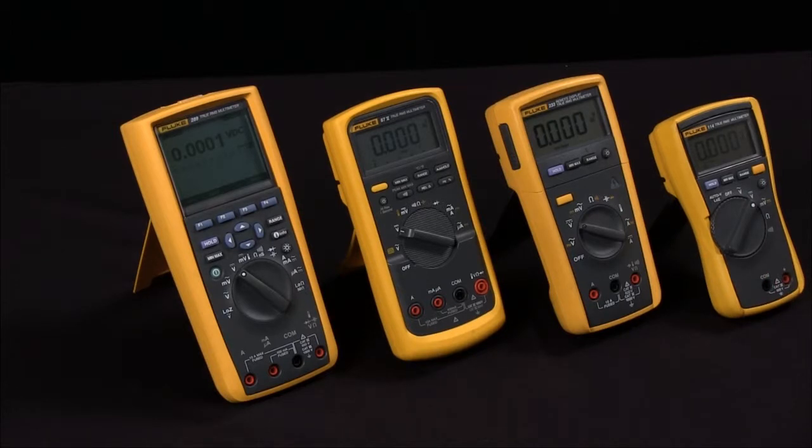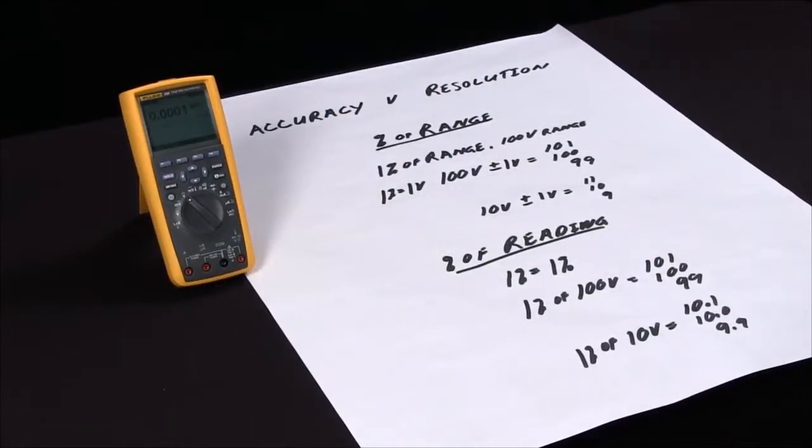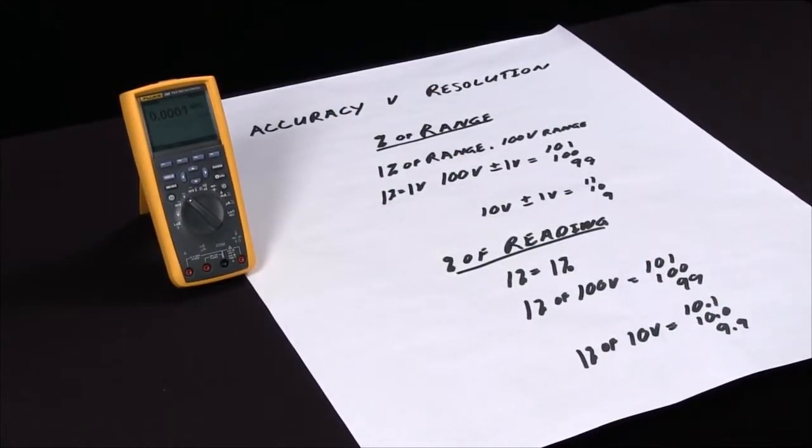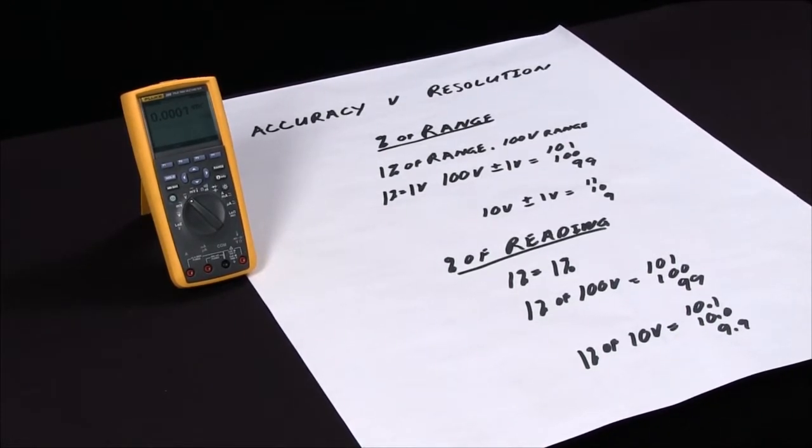Typically your higher cost multimeters will have a higher level of accuracy because it takes a much more precise circuit to measure things with more precision. Accuracy is an important specification when selecting an instrument because in many cases you want the accuracy of the meter you're using to be at least four times the accuracy of the measurement you're taking. A lot of times ten times is actually the goal.